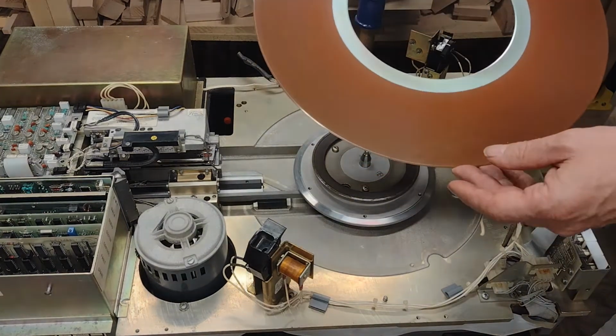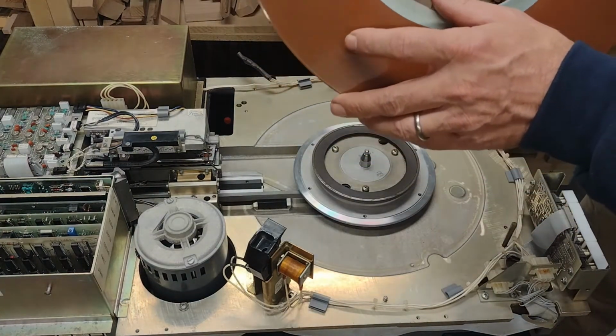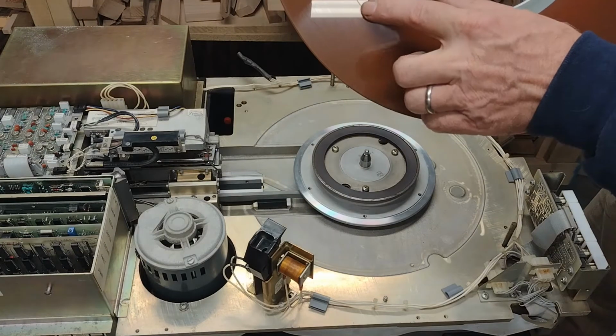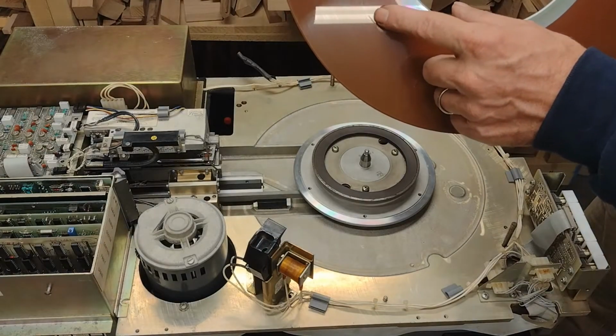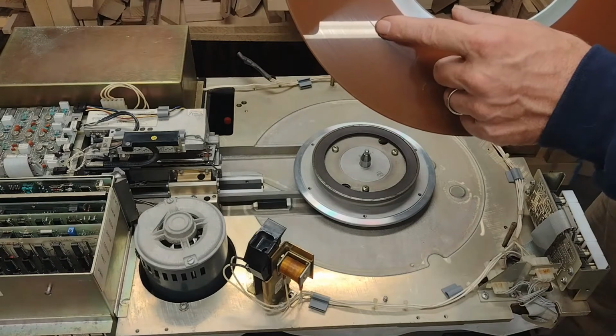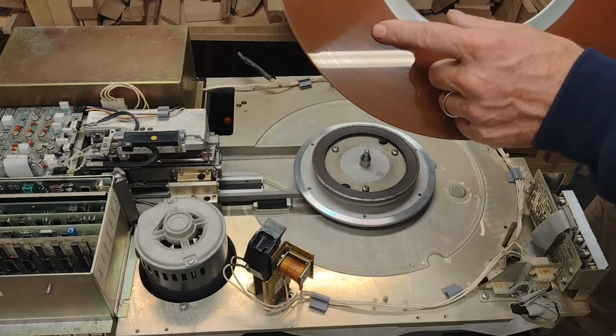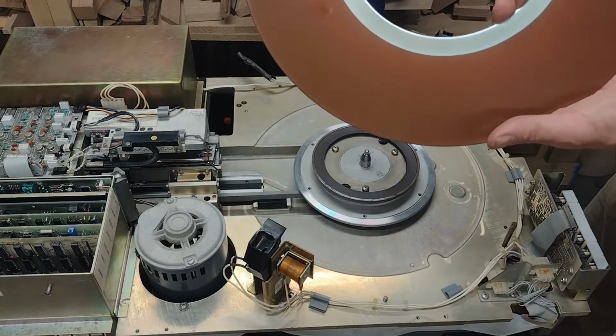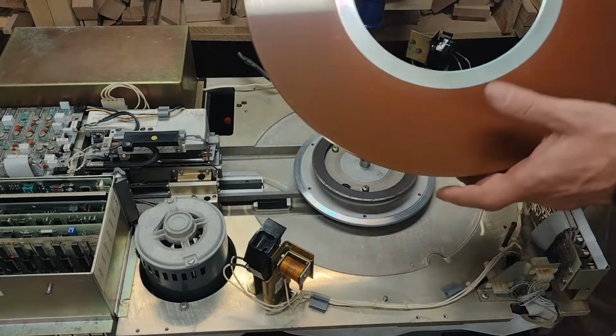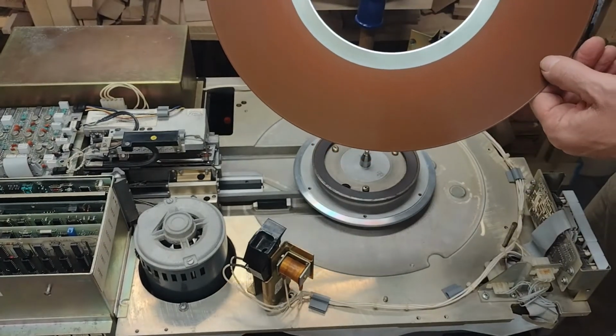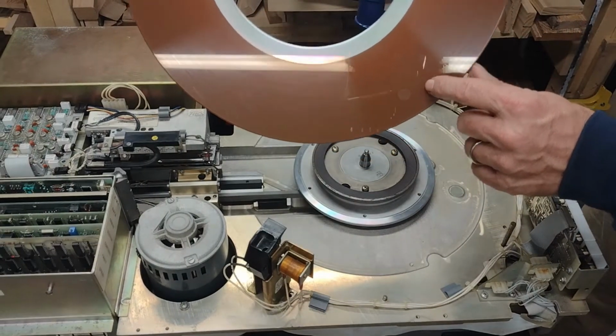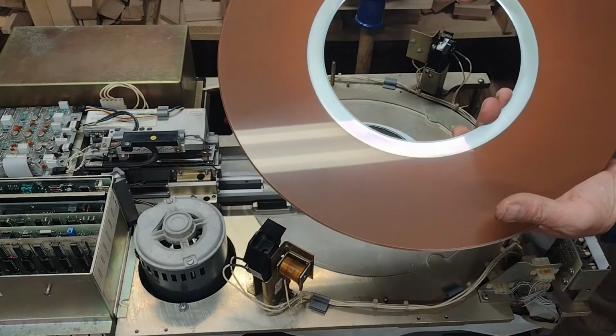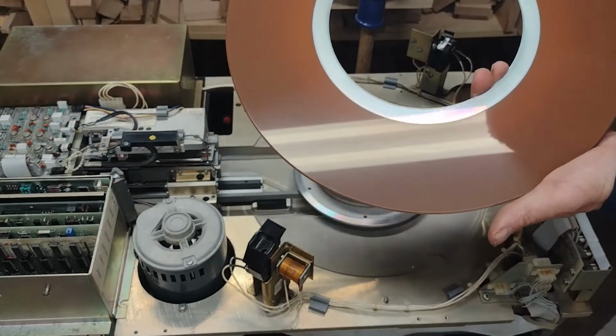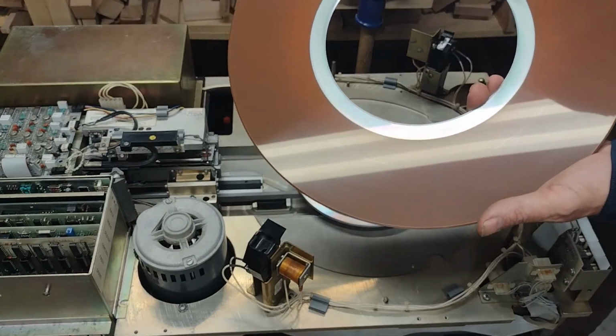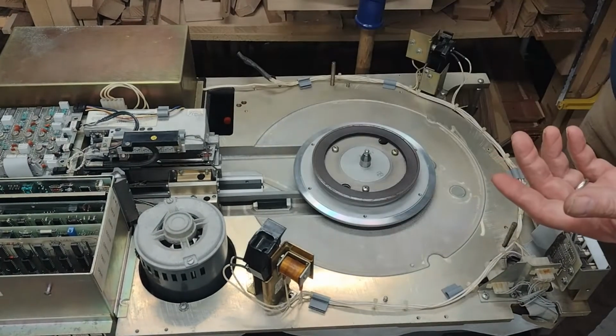We would look at the disk — I hope you can see right here, I can even feel it with my finger. Looks like a little piece of dirt got between the head and the disc. It didn't damage the disc, but it put some crap on there, you can see it right there. This side isn't too bad, but if I saw this at the customer site, I would get rid of it.